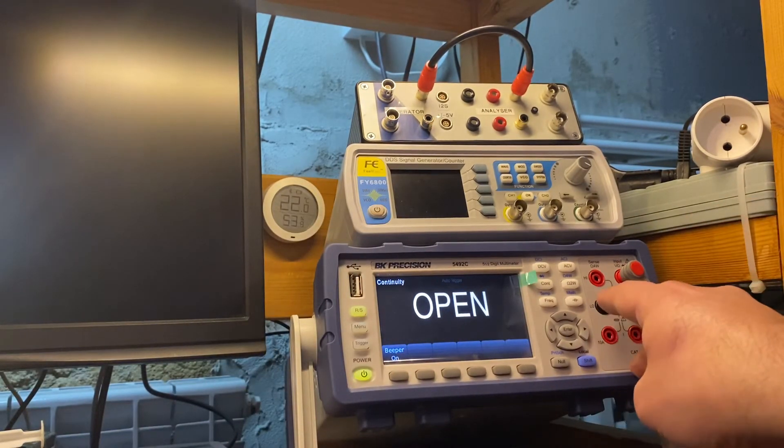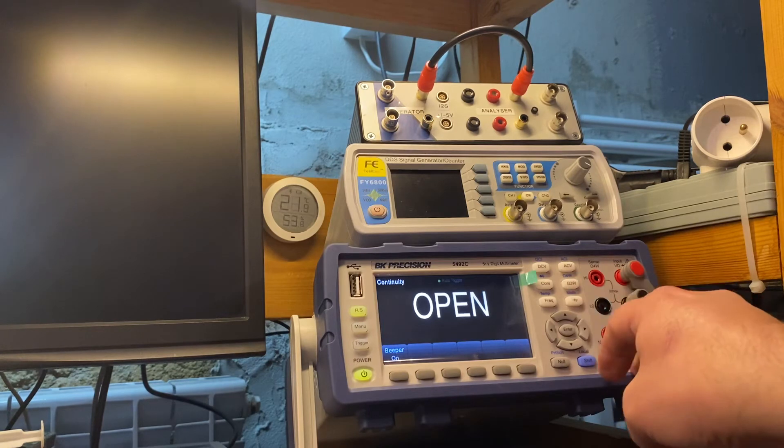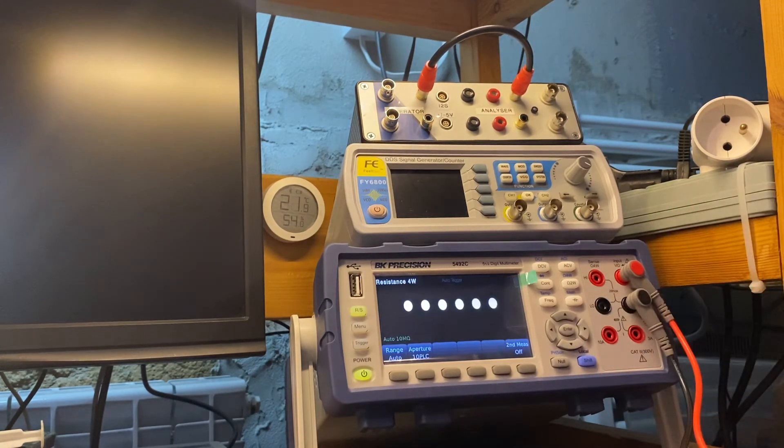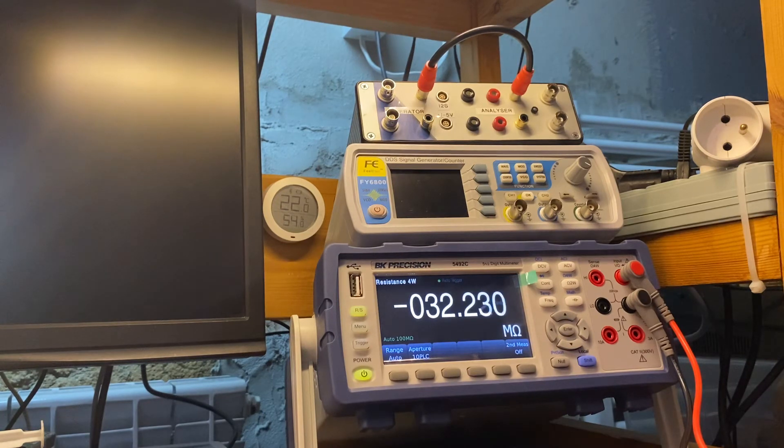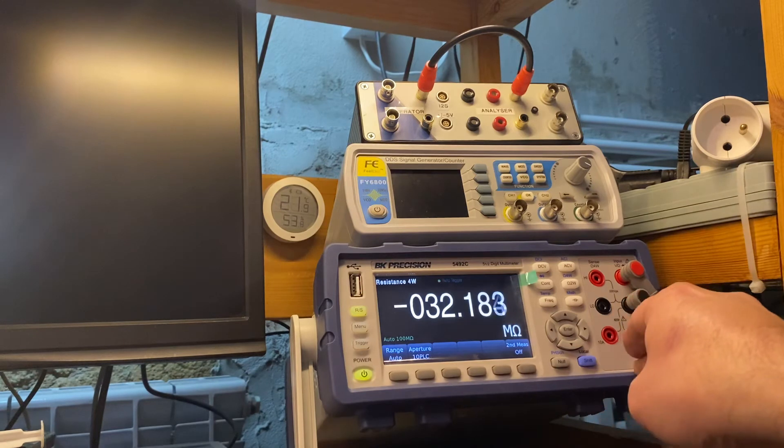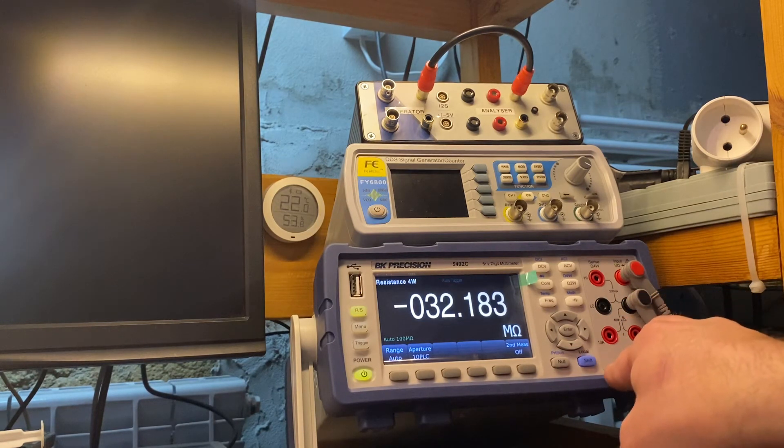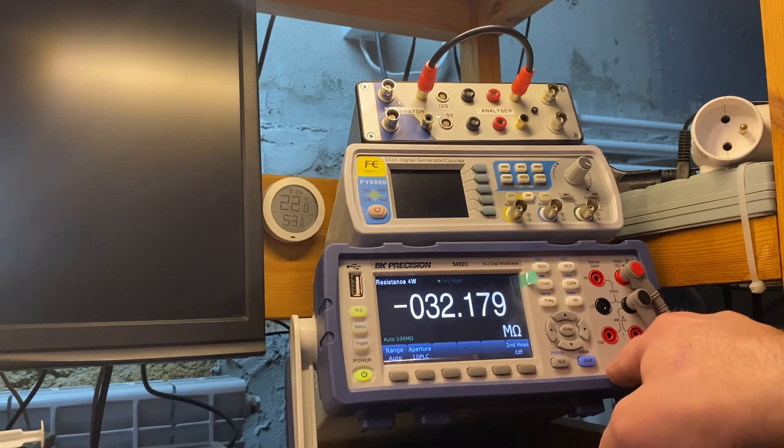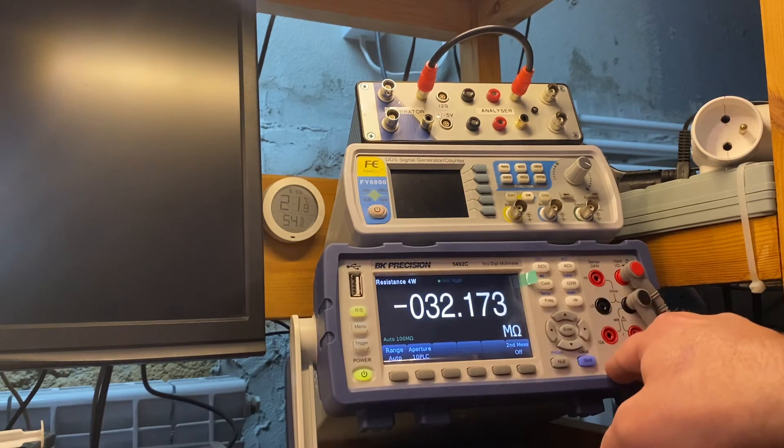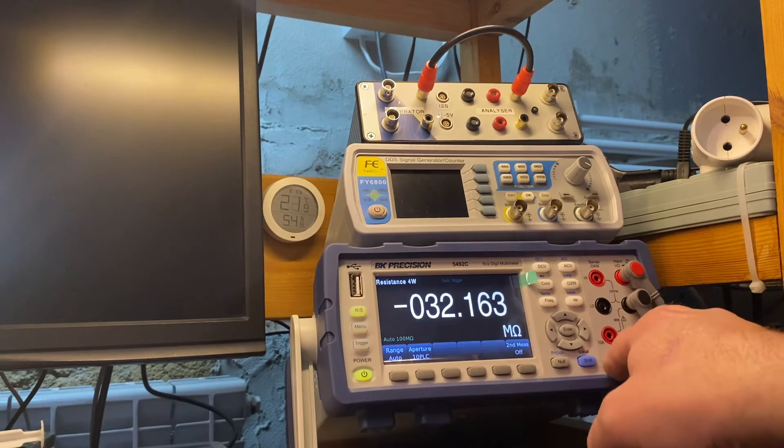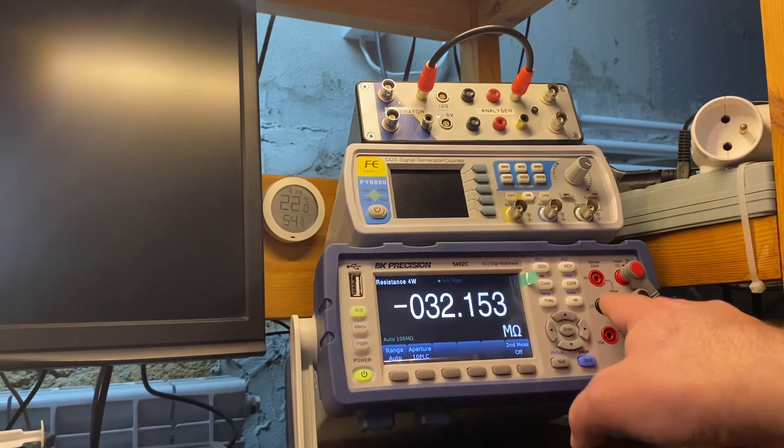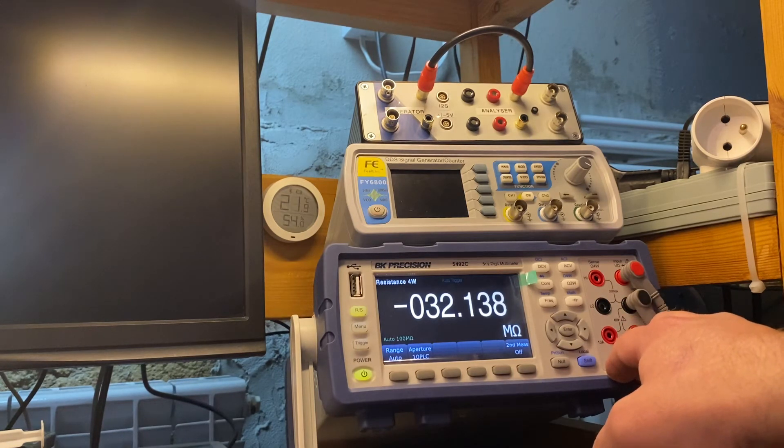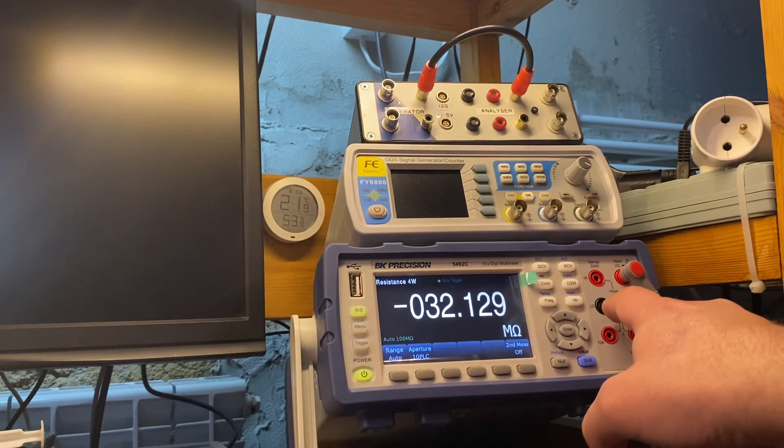And this looks strange too, but okay, this can be done different. This can look different than two-wire resistance because you need to connect two other wires to make correct measurements. But okay, we need to back to the continuity.